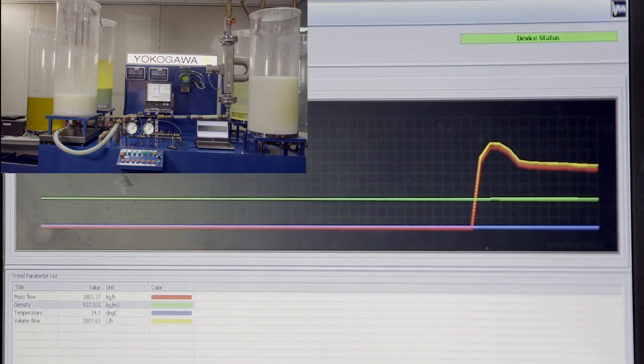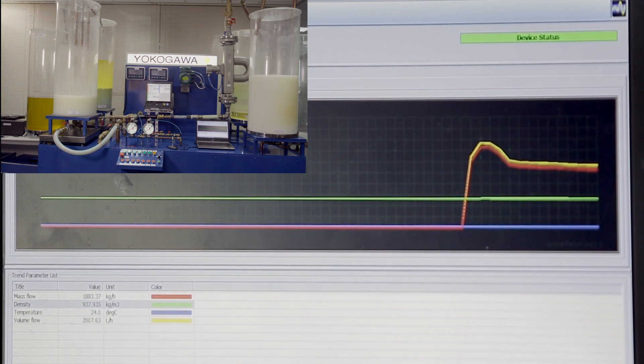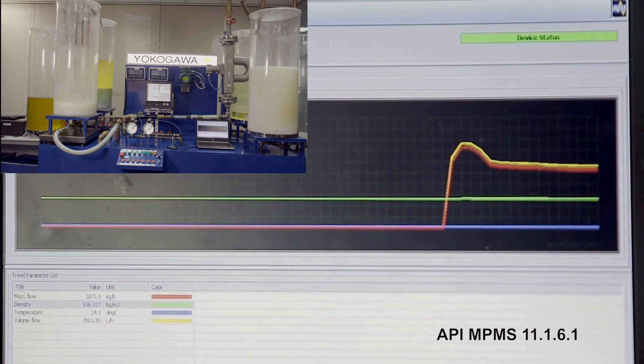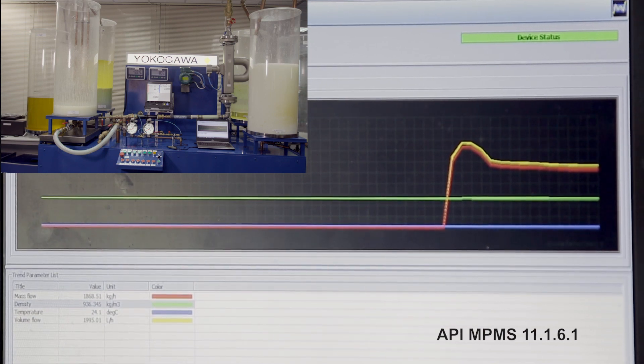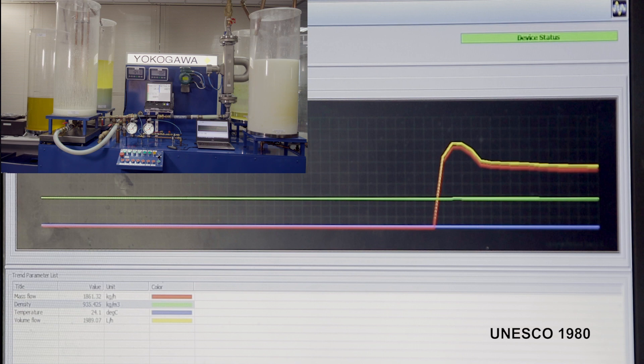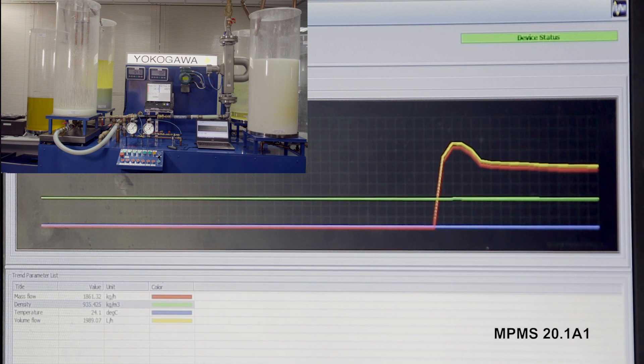It can also be observed that the volume flow is tracing the mass flow. When entrained gas or slug flow is detected by Rotamass, the advanced net oil computation algorithm kicks in and computes the density of oil based on the inbuilt API MPMS 11 table with pressure and temperature corrections. Water density calculation is done by built-in algorithms including SMOW, UNESCO 1980, MPMS 11.4, MPMS 20.1A1, and L. Dusoki equations.